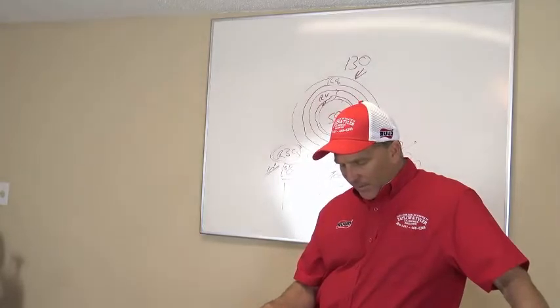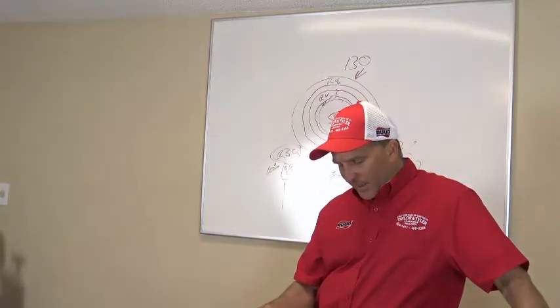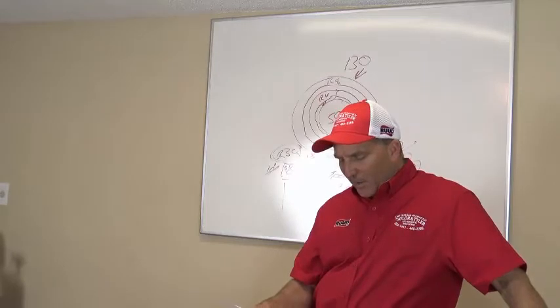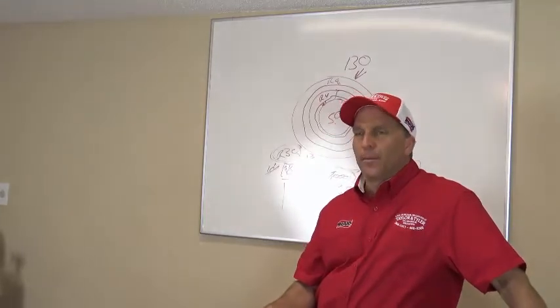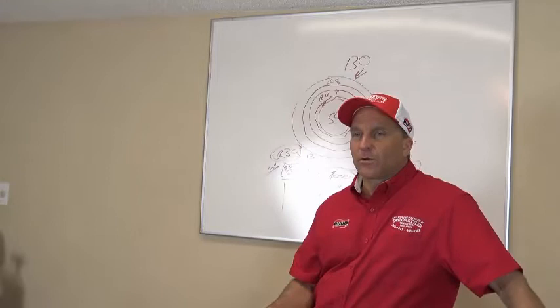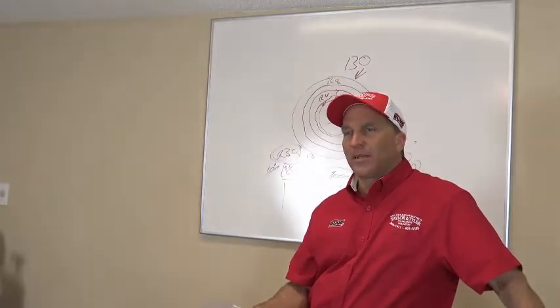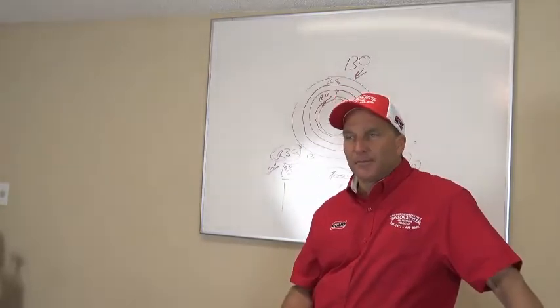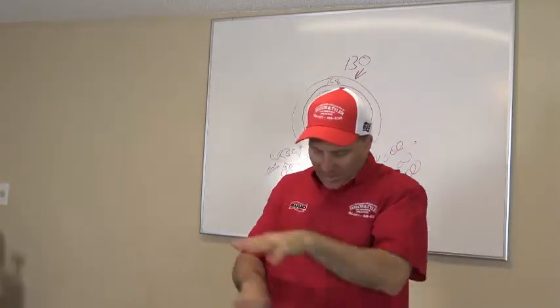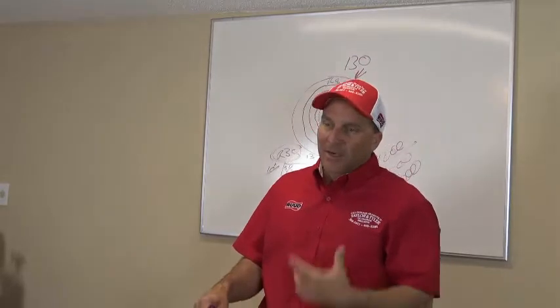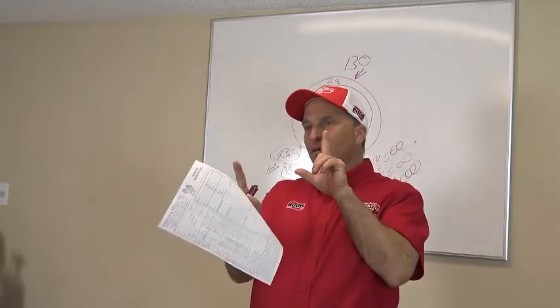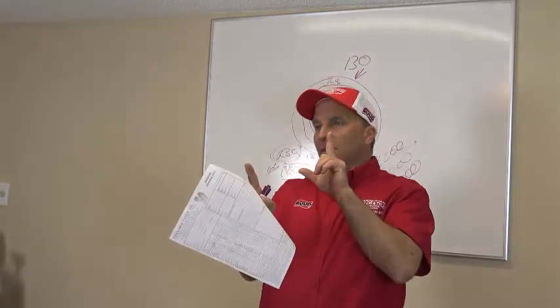Rubatex needs to be finished all the way to your P-trap. Is it not finished or is it missing? That Rubatex right there is for your coil. How many times do you go up to a vertical coil or a horizontal coil and it's missing Rubatex about 8 inches? And it keeps dripping down right onto the top of your furnace, and it causes the top of your furnace to rust out because it's constantly wet, because they got this much copper line with no Rubatex on it.